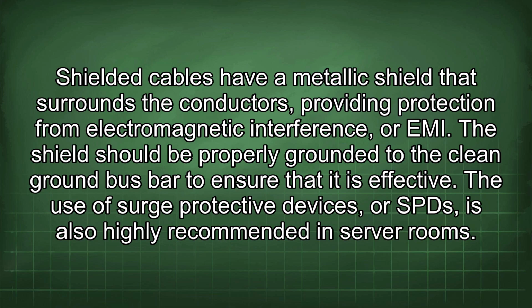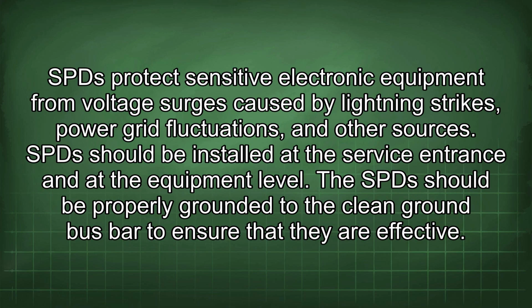The use of surge protective devices, or SPDs, is also highly recommended in server rooms. SPDs protect sensitive electronic equipment from voltage surges caused by lightning strikes, power grid fluctuations, and other sources. SPDs should be installed at the service entrance and at the equipment level. They should be properly grounded to the clean ground bus bar to ensure that they are effective.